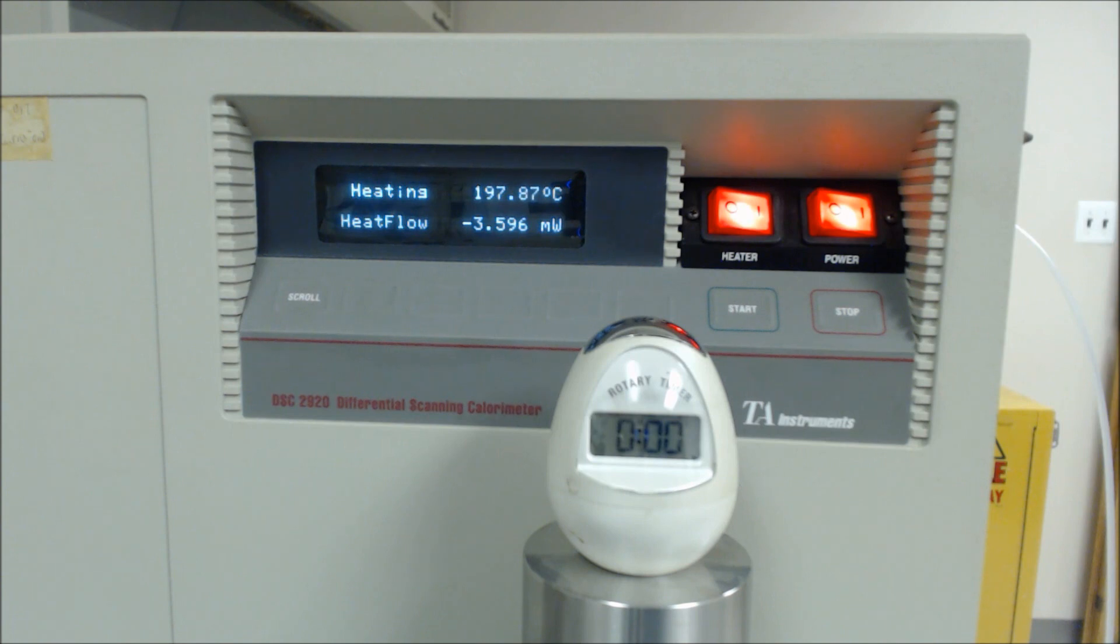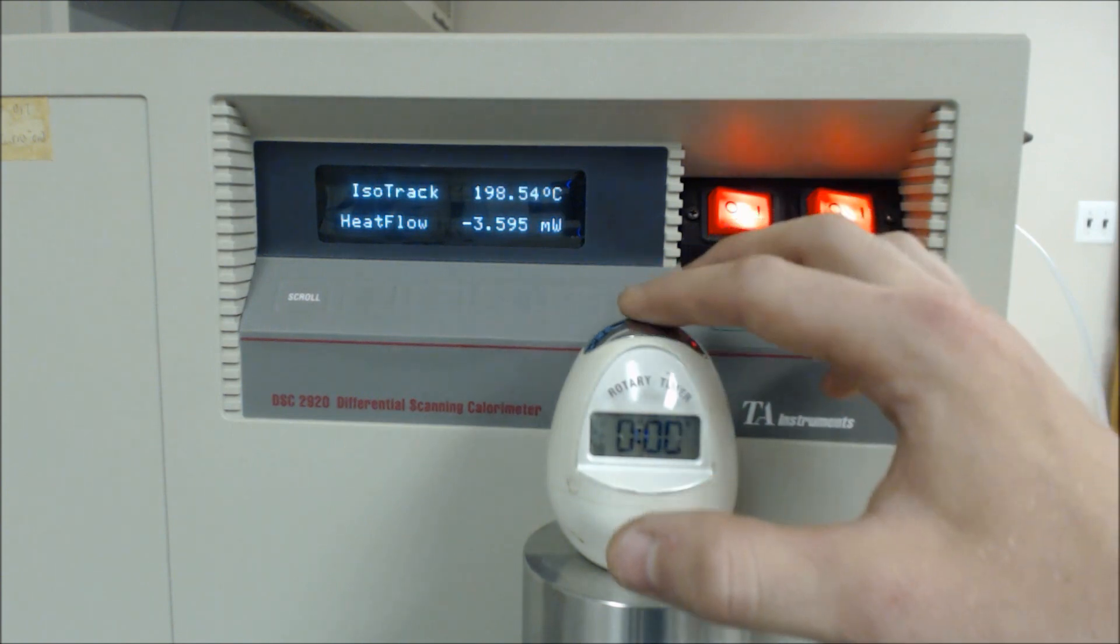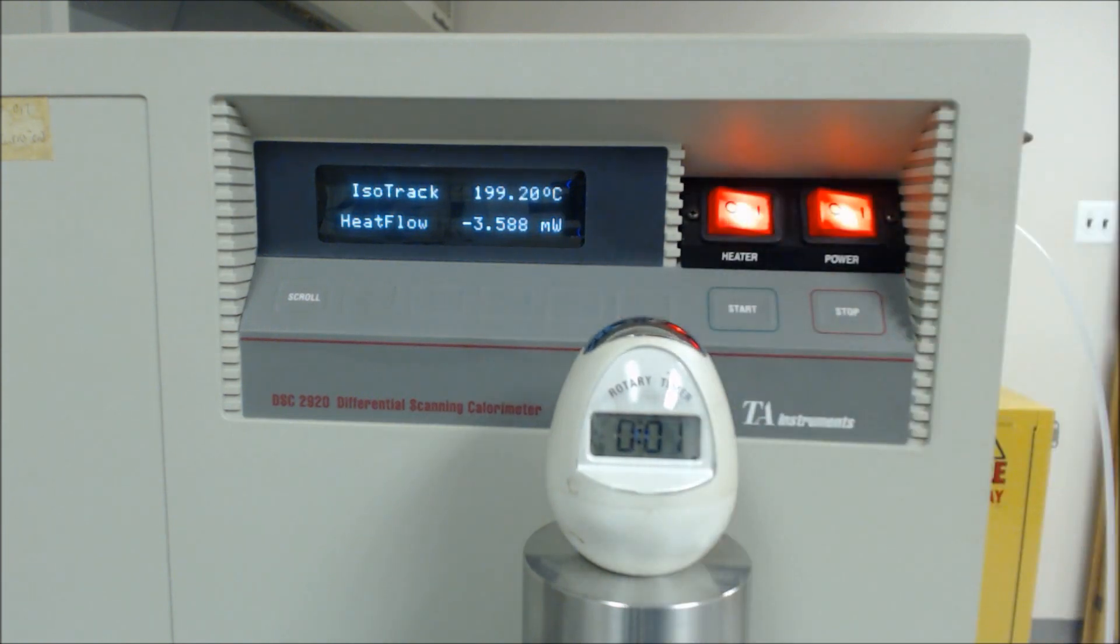After we reach 200 degrees C, the next phase of the test will begin. The first isothermal track phase lasts 5 minutes and essentially sits the cell at 200 degrees C while submerged in nitrogen gas. As you just saw, we started a timer at the beginning of the isotrack period to successfully count the 5 minute duration. However, the timer function is typically handled by the DSC's software. We're just using the egg timer to make this easier to follow on video.